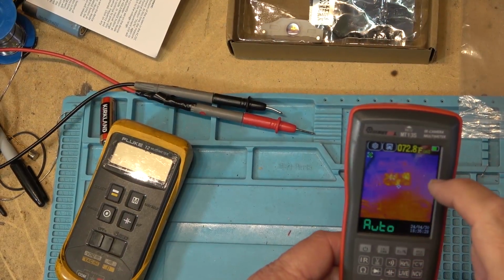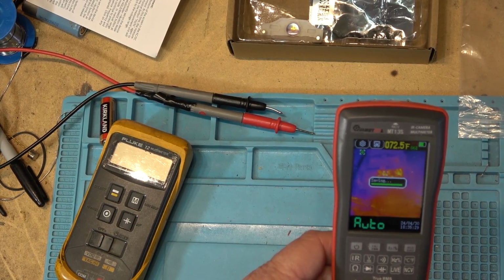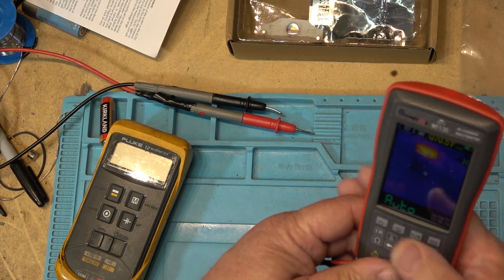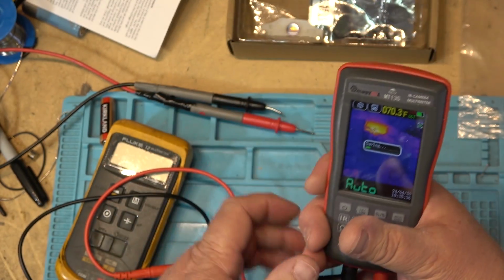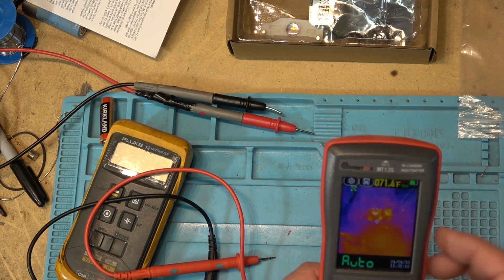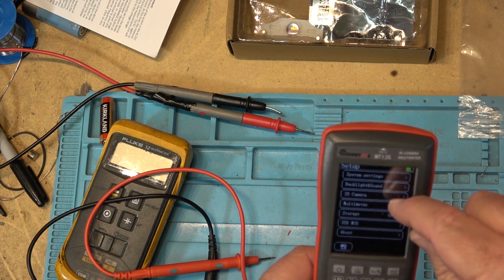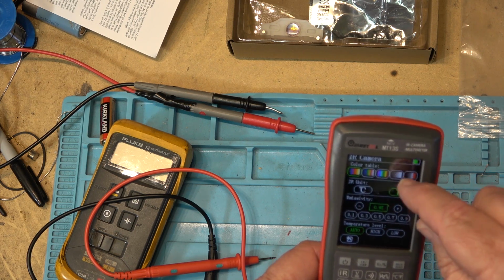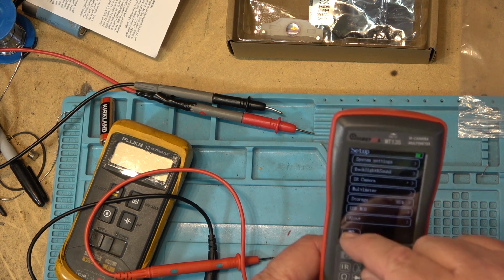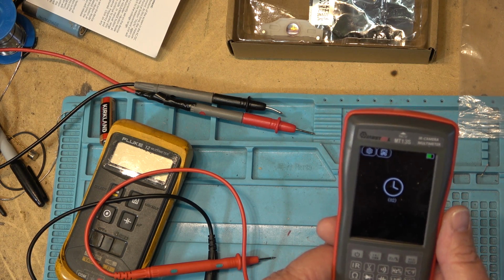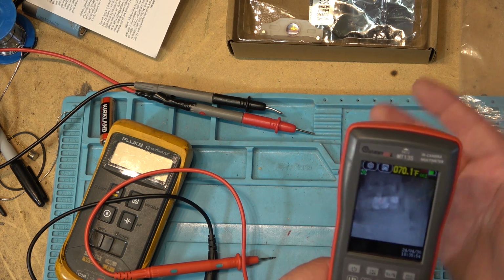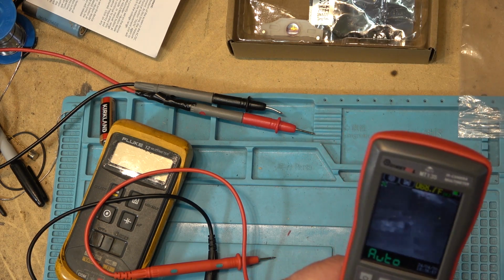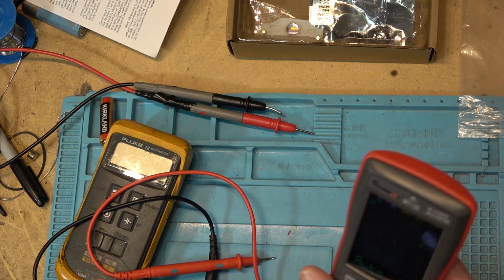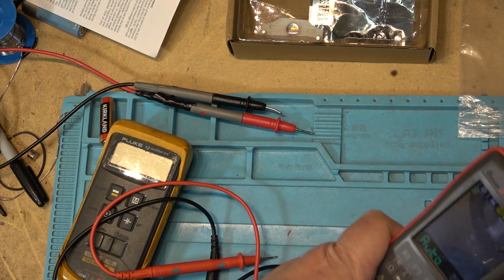Forgot to mention, if you tap here, that'll take a picture, so you can save your images. So if you've got something you're looking at, something that's hot, you just tap the screen right there. That's the save button. We can also change the view. If I go to settings and I go to IR camera, if we want to look at just a black and white image, we can select that one, and now we will see a white hot as opposed to a color image. Now you see white is hot and black is cold. A lot of times when you're looking at stuff on infrared, that's what you want to see. You want to look at the actual temperature in black and white. Makes it easier to see what you're doing.